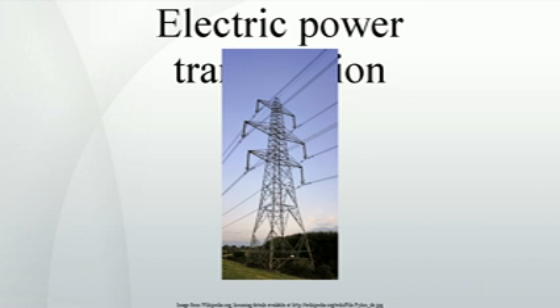Subtransmission. Subtransmission is part of an electric power transmission system that runs at relatively lower voltages. It is uneconomical to connect all distribution substations to the high main transmission voltage, because the equipment is larger and more expensive. Typically, only larger substations connect with this high voltage. It is stepped down and sent to smaller substations in towns and neighborhoods. Subtransmission circuits are usually arranged in loops so that a single line failure does not cut off service to a large number of customers for more than a short time.